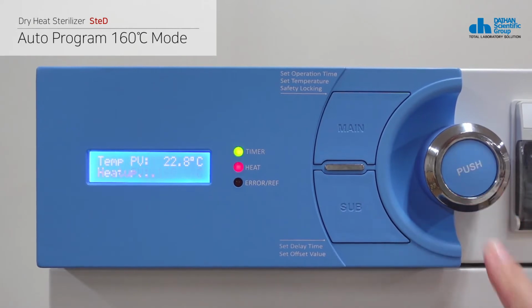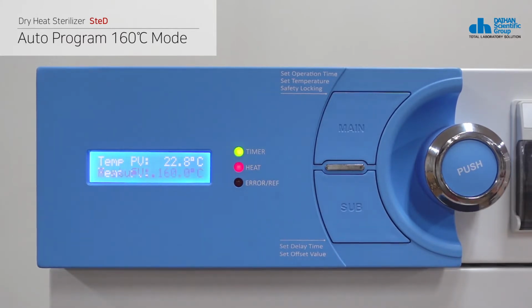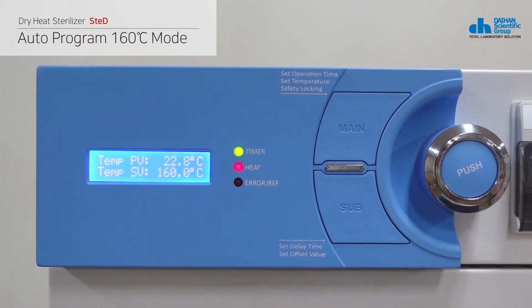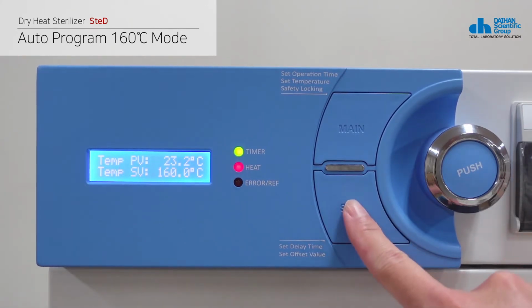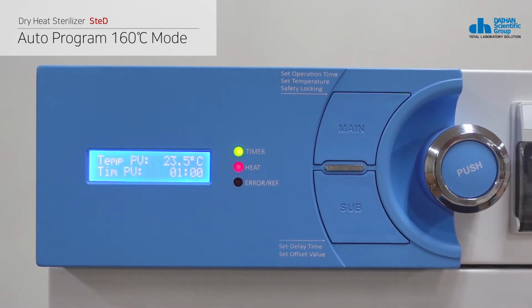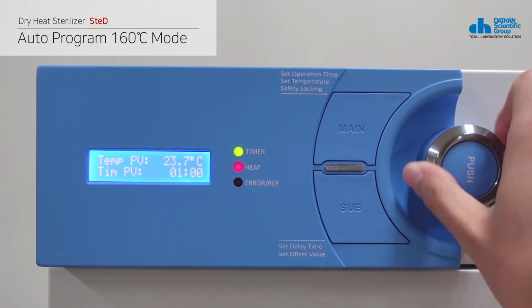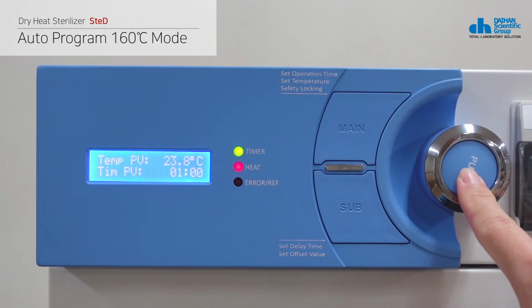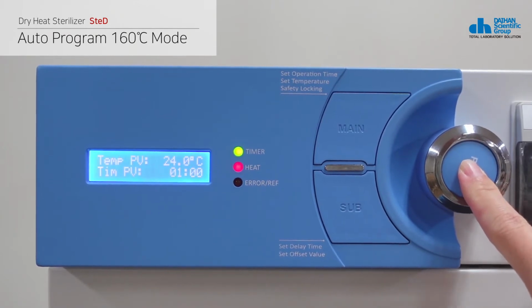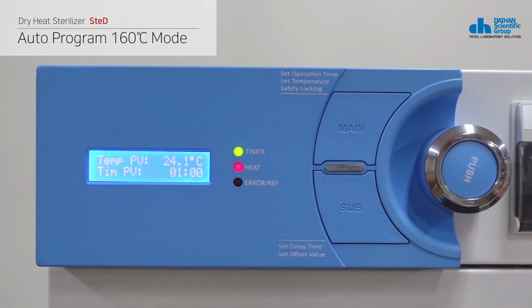During heating operation, the current temperature is displayed at the top of the LCD, alternating between the current status heat up message and the set temperature at the bottom. At this time, when the sub button is pressed, the locking mode is set. The setting does not change when the knob is turned and the push button remains pressed. Locking mode is recommended during product operation.